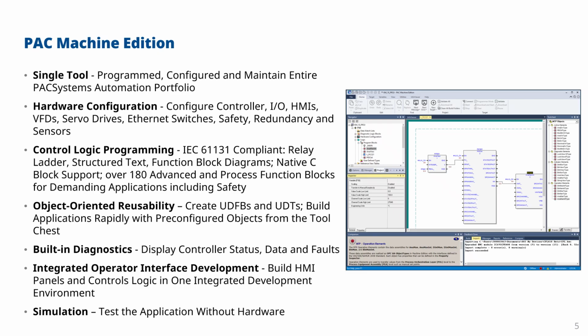From the IEC 61131-3 point of view, we support relay ladder, structured text and function block diagrams. We also support native C blocks. The idea here is you can compile a C block using an open source C compiler that we provide, and then run those C blocks inside the controller so they can communicate with the PLC's data table, or you can control them using parameter access. That's outside the scope of this slide deck, but I may cover it in another one later. As well as the standard relay ladder, structured text and function block type function calls, we also have over 180 advanced and process function blocks which allow you to implement demanding applications, including safety under IEC 61508.